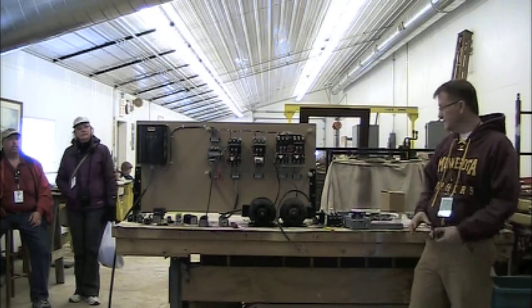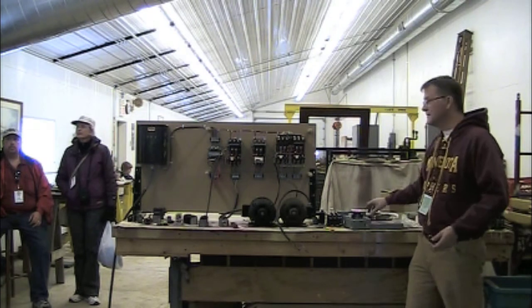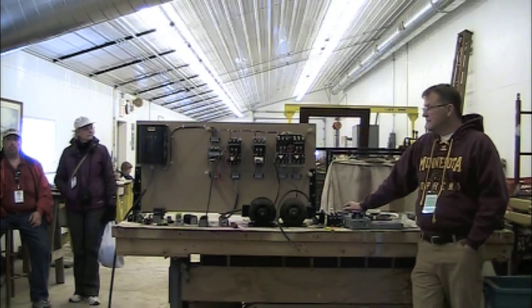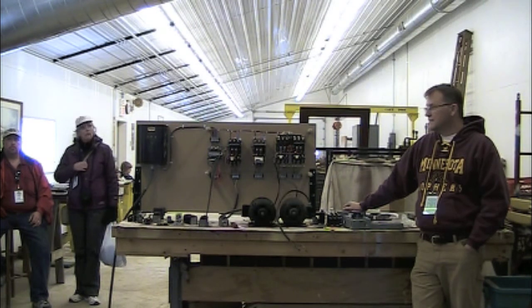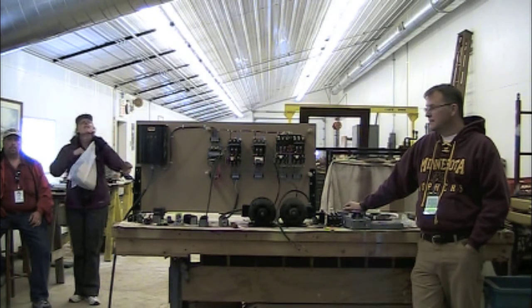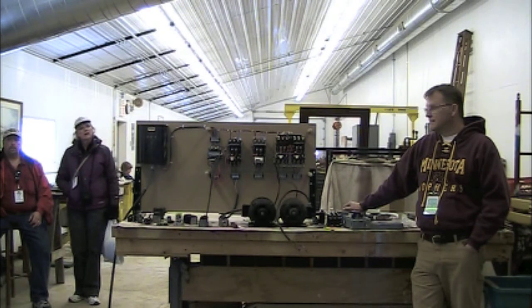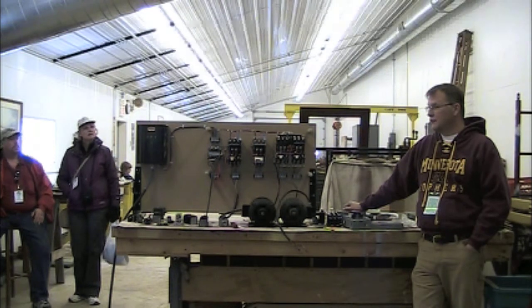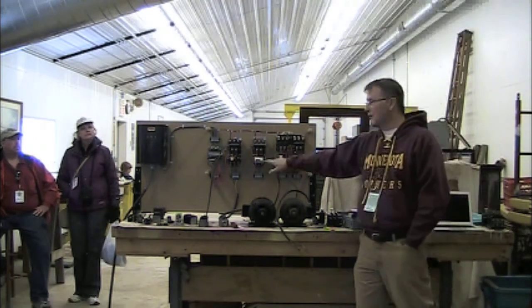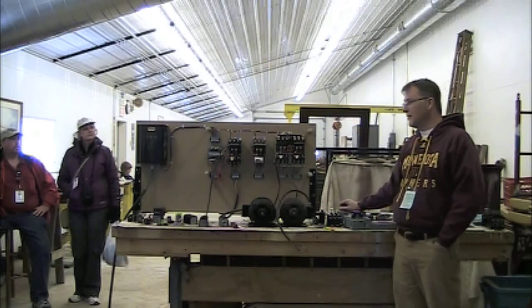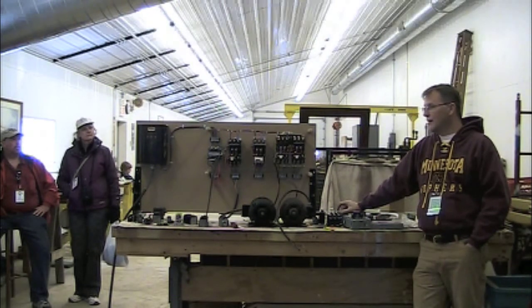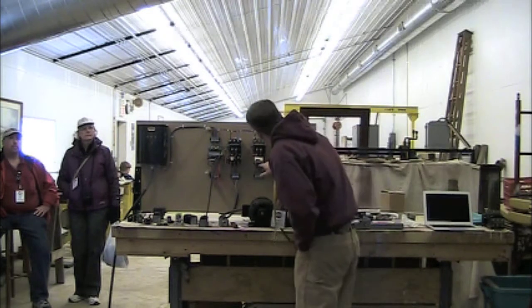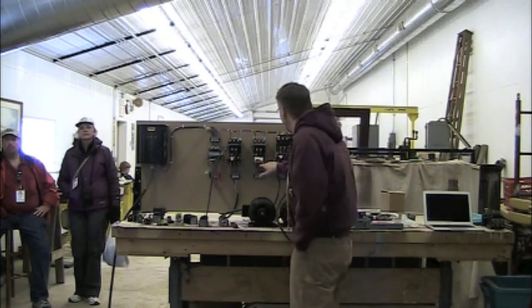Ray, is there any sort of codex that gives a one-to-one mapping from the NEMA 1, 2, 3 to the 95, 97, whatever it is in the IEC? Is IEC consistent enough? IEC is very consistent in their terminal wiring. They've got a whole array of numbers depending on what you're doing in the whole control wiring scenario. These are well labeled because it just says NC, and it just says 96 and 95 and 96 next to it.